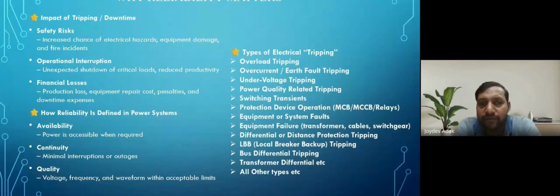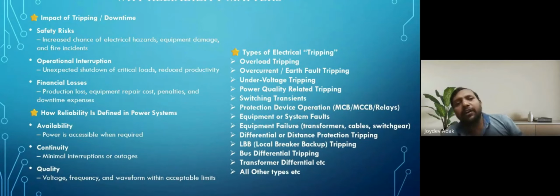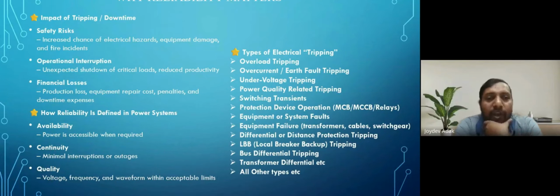Equipment or system faults. Next one is equipment failure: differential or distance protection tripping, LBB (local breaker backup) tripping, and bus differential tripping. These are applicable only in switchgear. Local breaker backup protection is used when the system is 132 kV and above. For 220 kV and above, we use differential and LBB both. LBB and bus differential protection are the vital and complex main protection of switchgear.